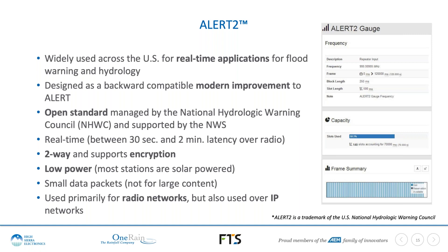Almost every agency in the U.S. with an Alert 2 network forwards data to the Weather Service as part of their forecasting and warning process. It's real time — in the Alert 2 context, data gets there between 30 seconds and two minutes after it's recorded. That time delay is typically related to how many gauges or sites you have on your network. With 200 sites there'll be longer latency; with 20 sites, latency can get down to five seconds.